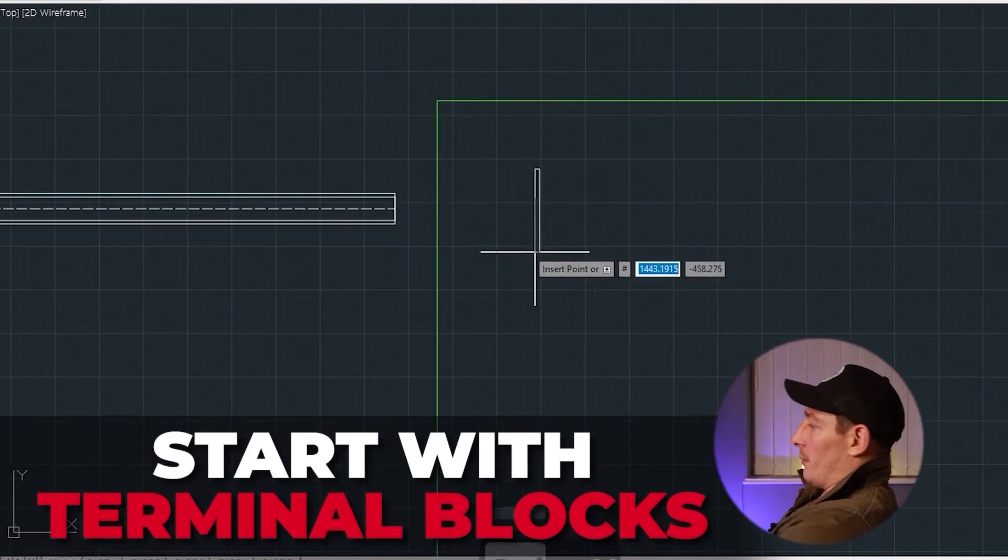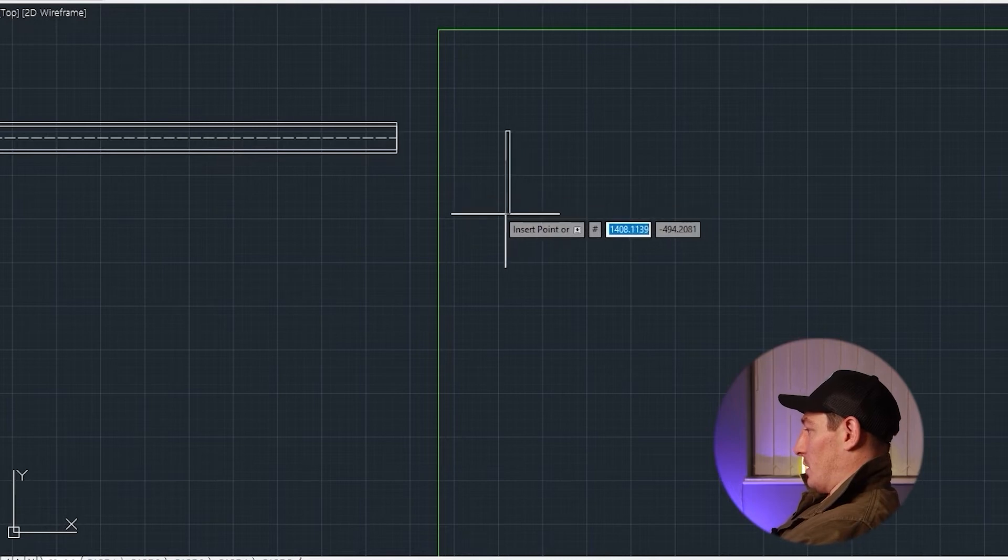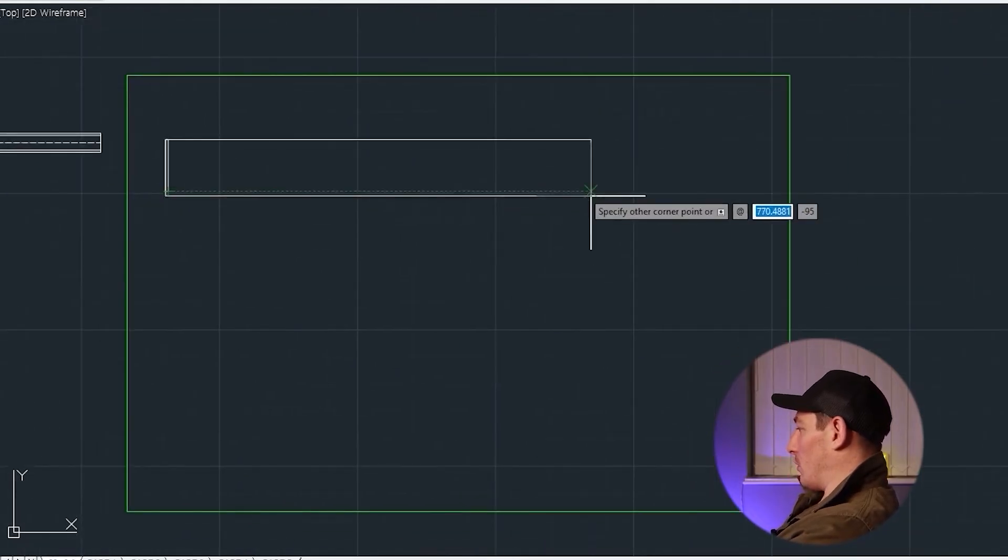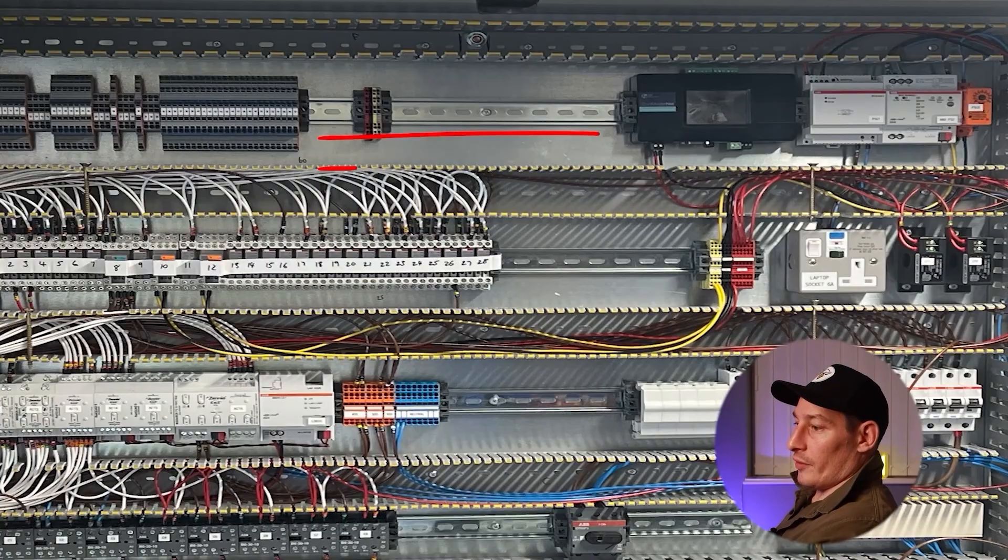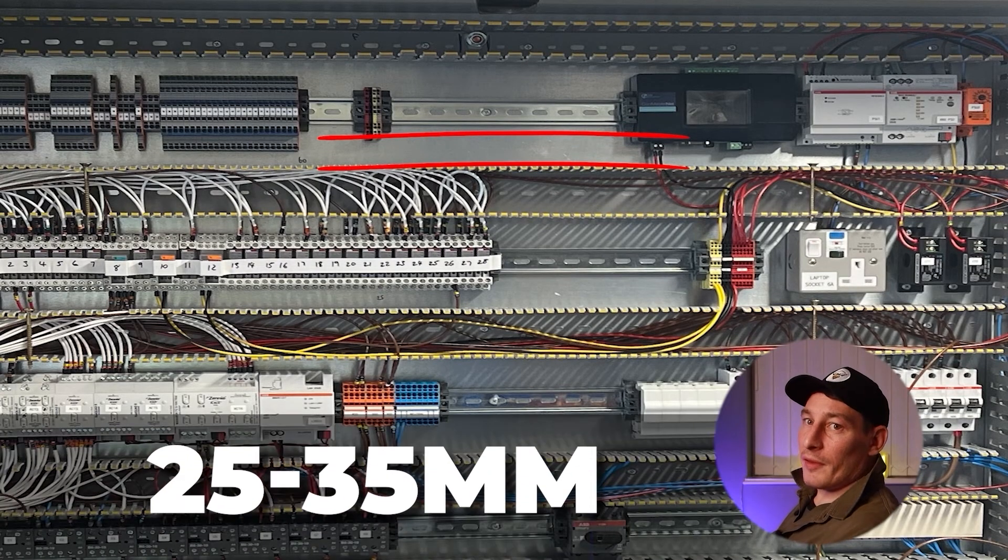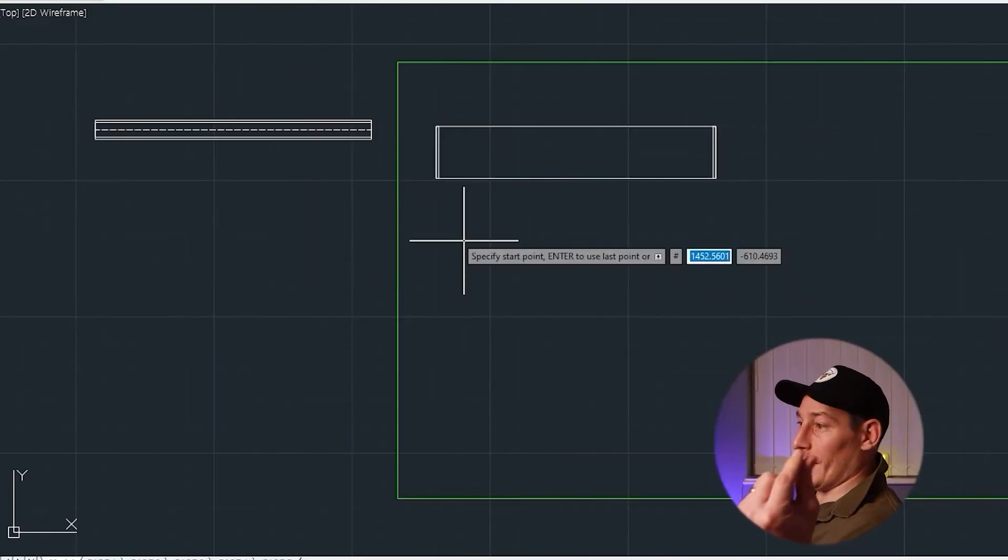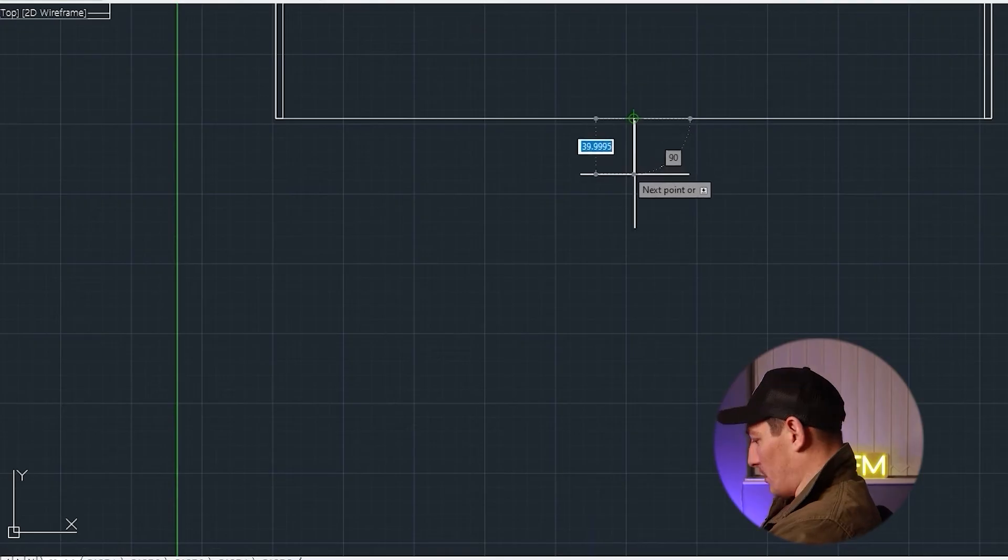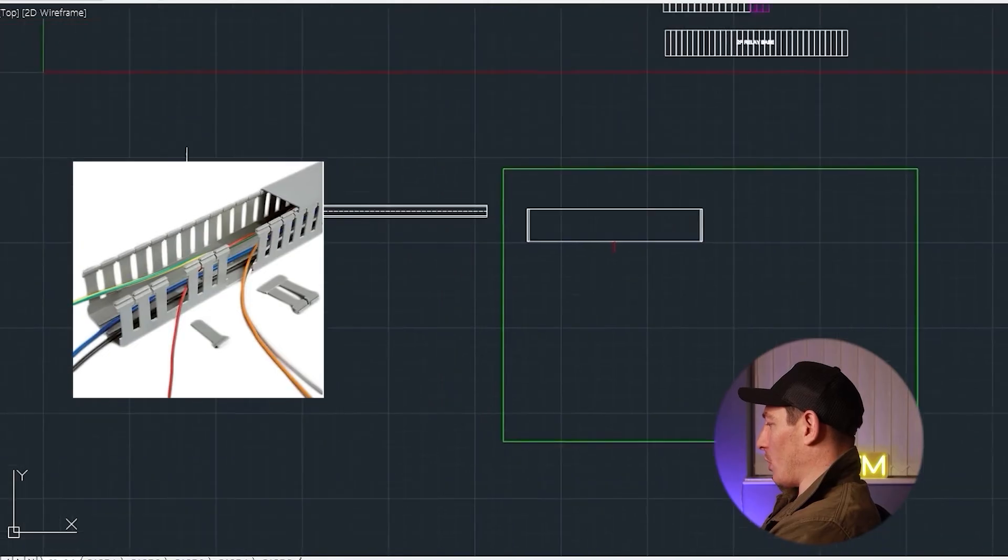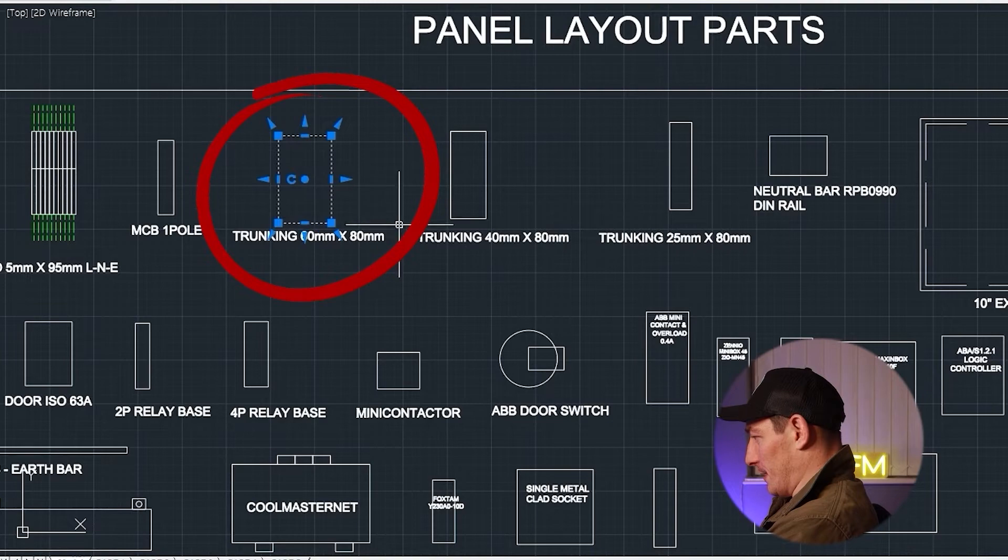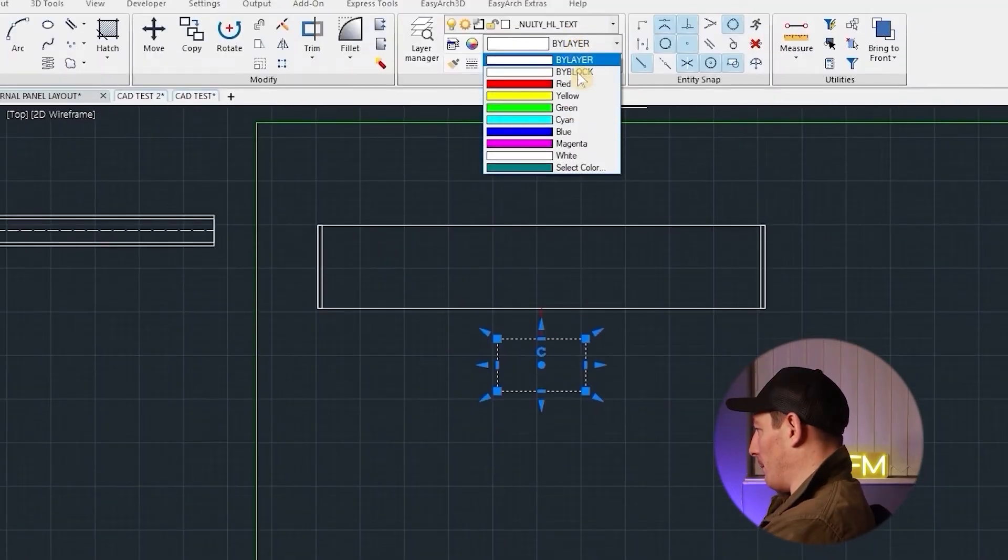This panel is going to be a top cable entry, so I'm going to start with the terminal blocks at the top. There's going to be a bit of trunking along the top row as well, so I reckon terminals are going to start about here. Because I don't know how many I need at the moment, I'm just going to go rectangle, move that across something like that. And then for the spacing between components and trunking, I try and keep a space of around 25 to 35 millimeters so there's enough room to get your finger and thumb in there to do the wiring. So I'll click there, I'll type 35, and I'll highlight that in red.